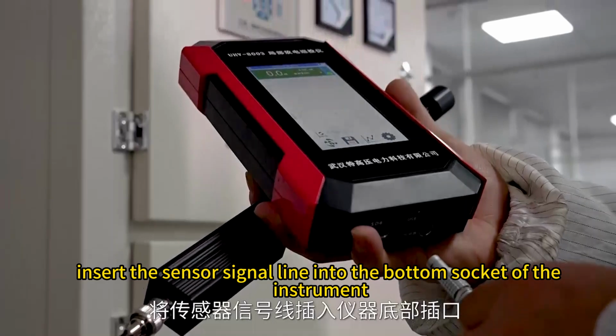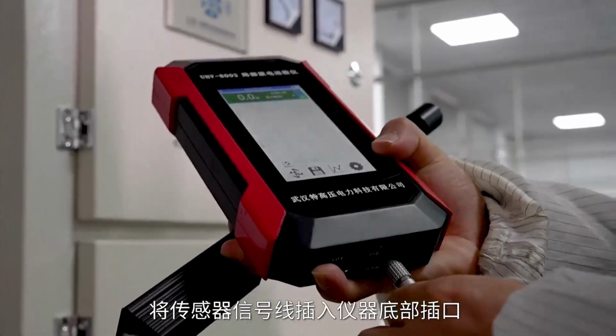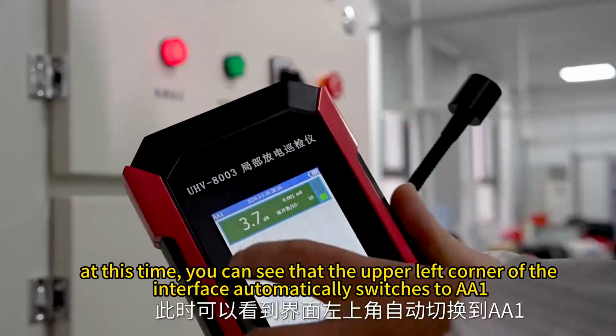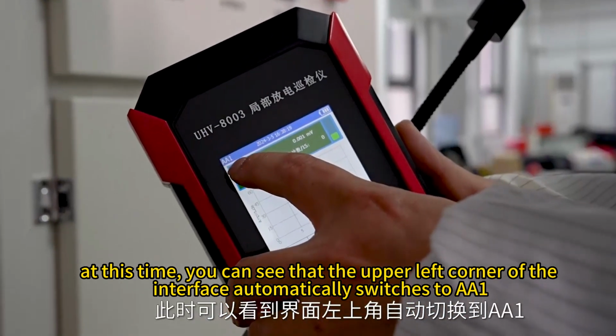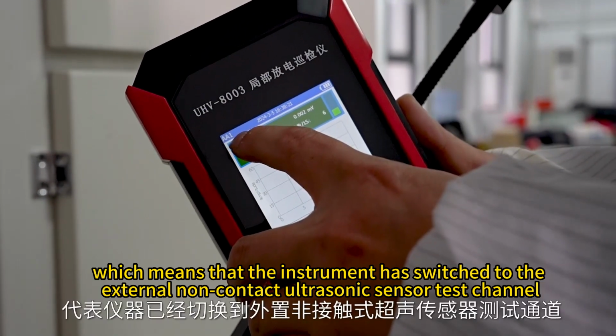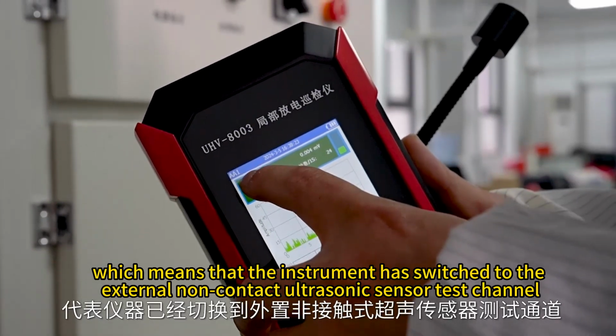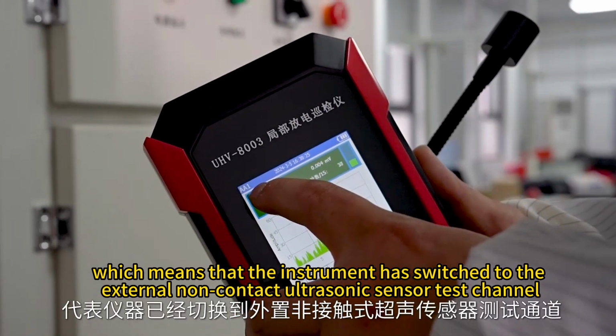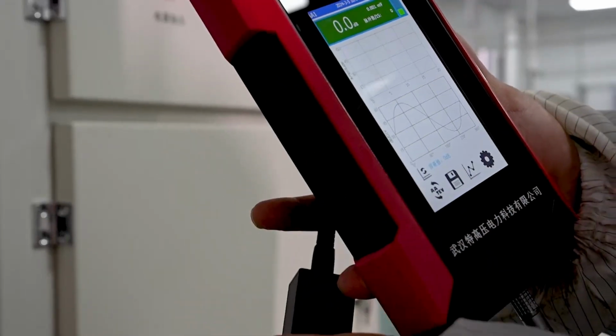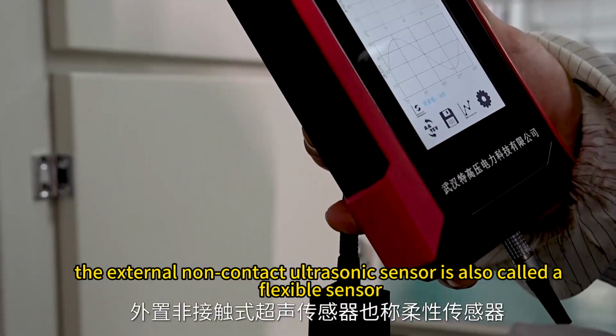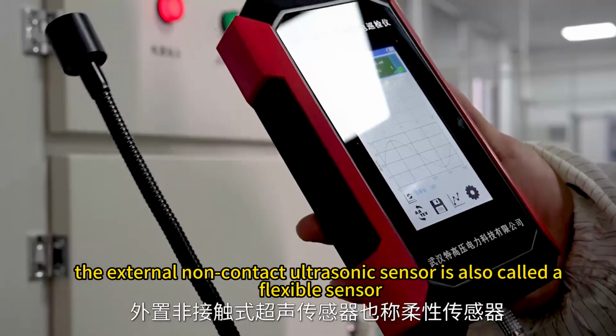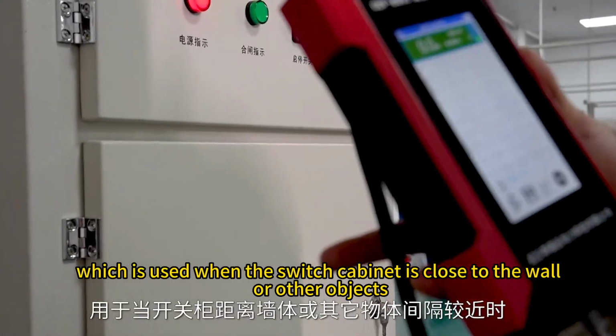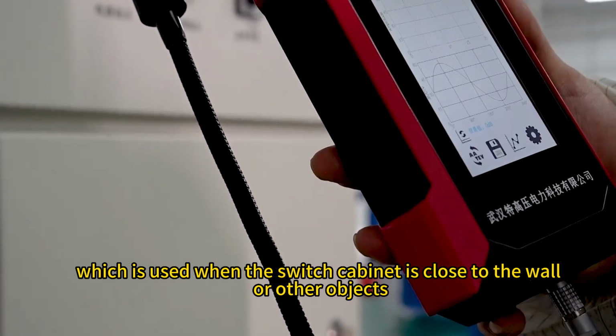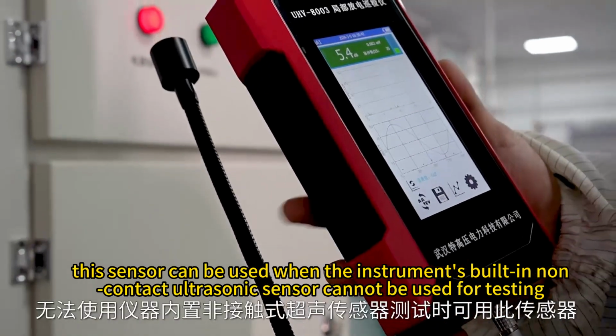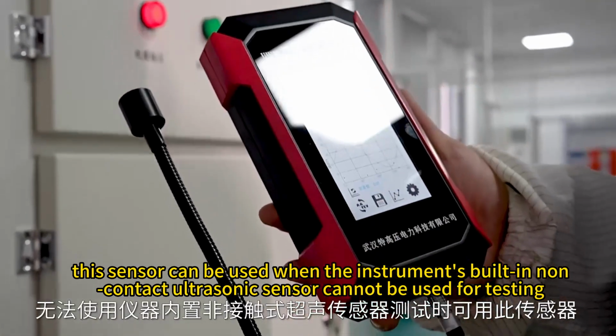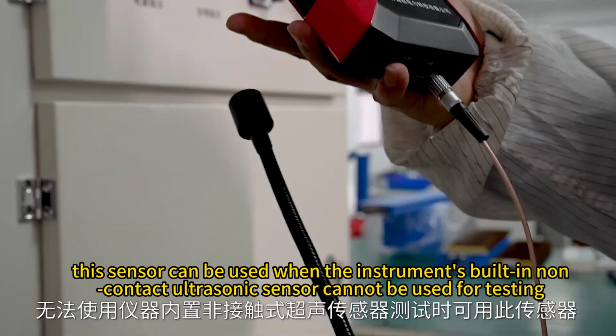Insert the sensor signal line into the bottom socket of the instrument. At this time, you can see that the upper left corner of the interface automatically switches to AA1, which means that the instrument has switched to the external non-contact ultrasonic sensor test channel. The external non-contact ultrasonic sensor is also called a flexible sensor, which is used when the switch cabinet is close to the wall or other objects. This sensor can be used when the instrument's built-in non-contact ultrasonic sensor cannot be used for testing.